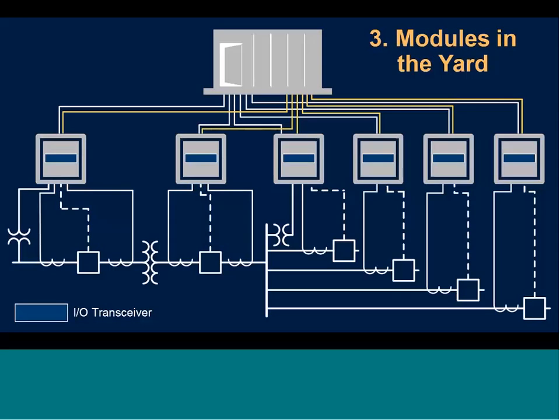What that would look like architecturally with our example is we would still have that hardwired connection from the cabinet all the way back to the control house because we still have our analog signals. But now we're also running, generally in the same trench, a fiber optic cable for communications purposes to transmit our I/O signals to that transceiver.